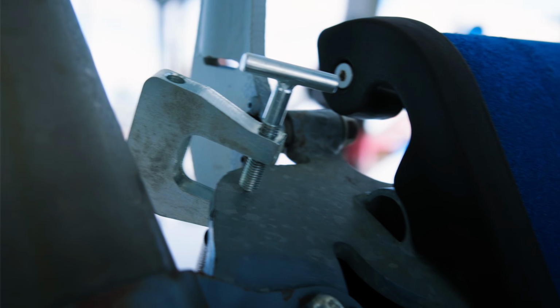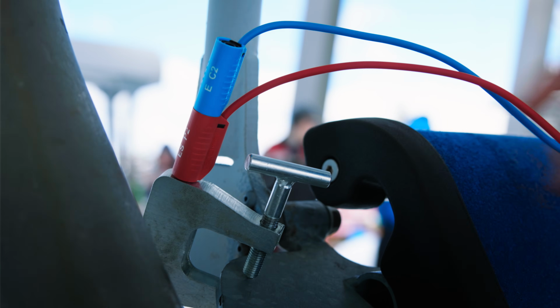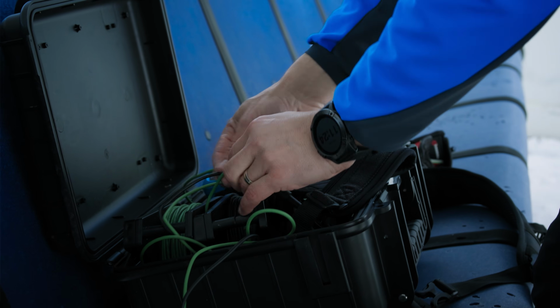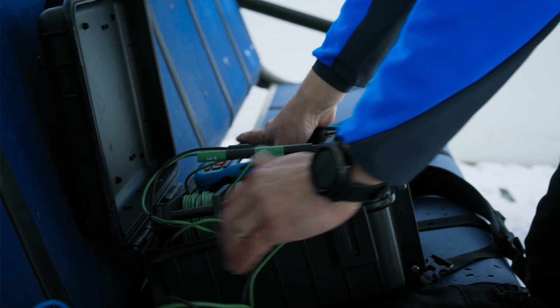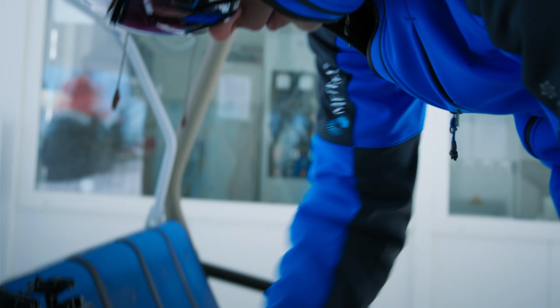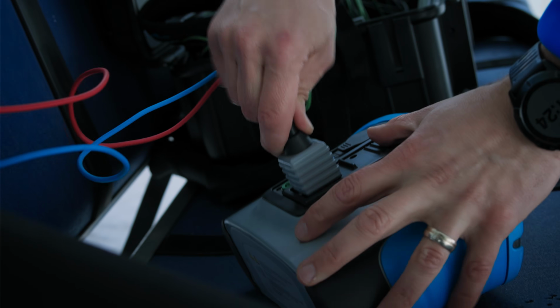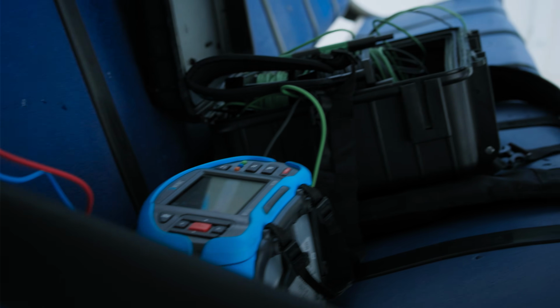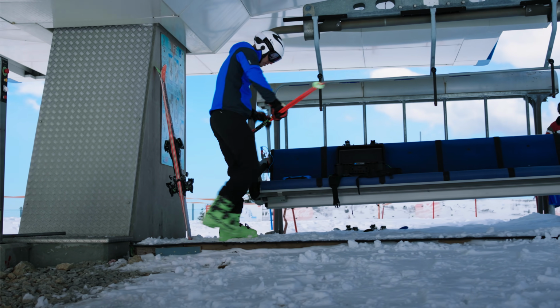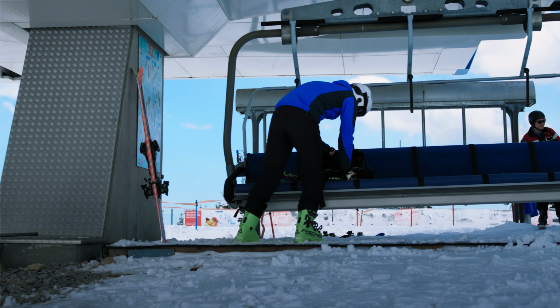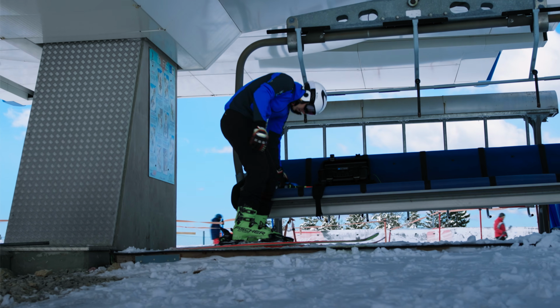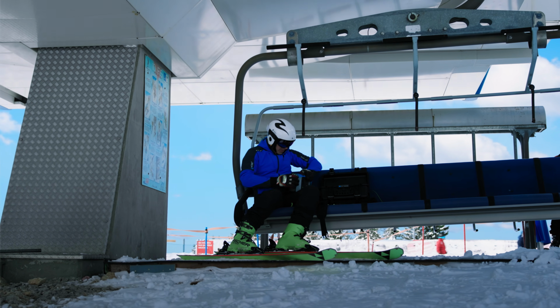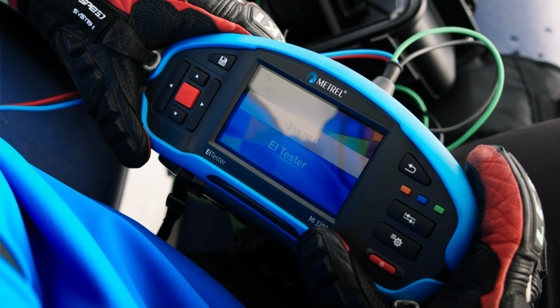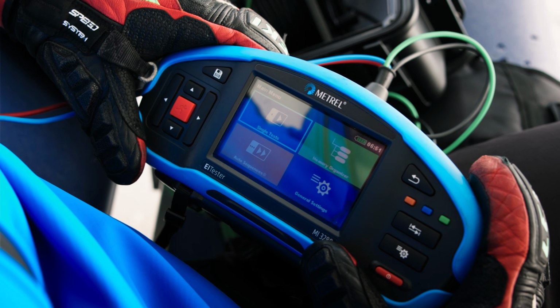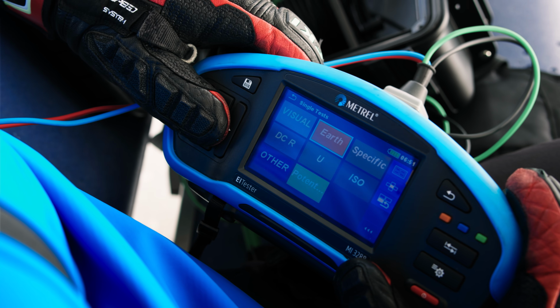We begin by connecting the 4-wire extension leads to the G-clamp and the extension rod, allowing temporary contact with each tower. Using the MI3288 tester, the measurement procedure is straightforward and identical for both gondolas and chairlift towers. But it requires the use of the Kelvin method to ensure accurate and reliable results. Finally, the tester is set to Earth mode.